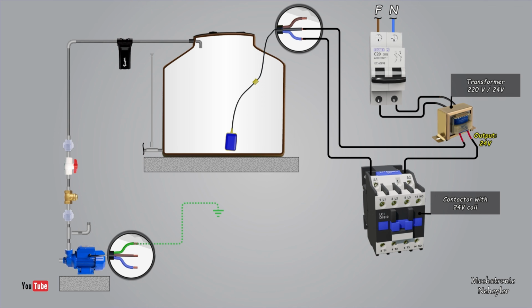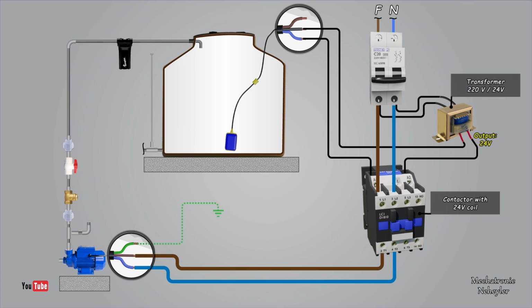To connect the electric pump. From the output of the thermomagnetic switch, the cables are connected to the power contacts of the contactor, and from its output to the electric pump. So that would be the whole connection. In this way we isolate the control part that corresponds to the float, with respect to the power part, which is made up of the electric pump. Thus, there is less probability of receiving an electric shock if water or moisture passes through the float or any connection.